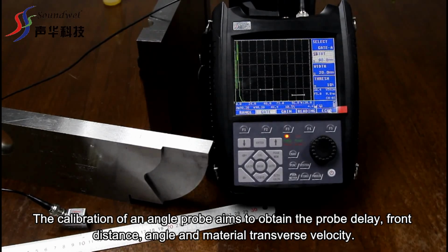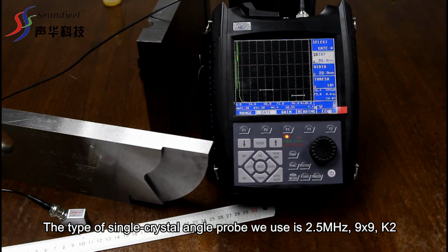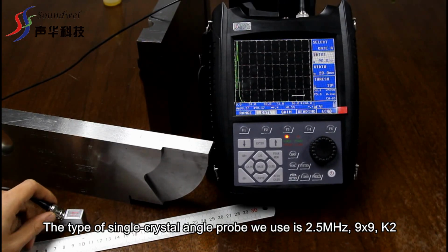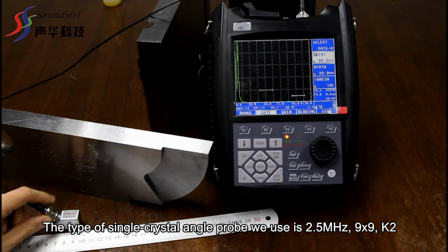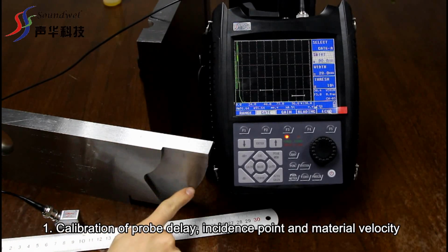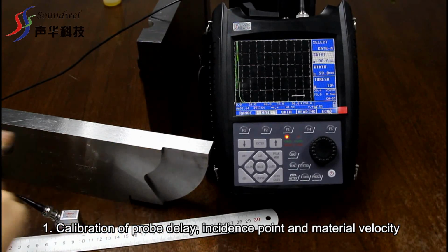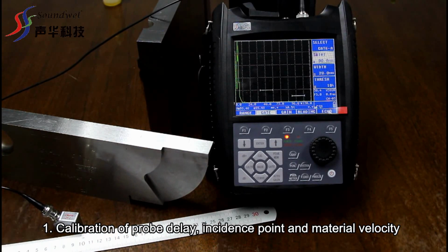Next, we introduce the auto-calibration of a single crystal angle probe. The type of single crystal angle probe we use is 2.5 MHz 9x9 K2. 1. Calibration of probe delay, incidence point, and material velocity.